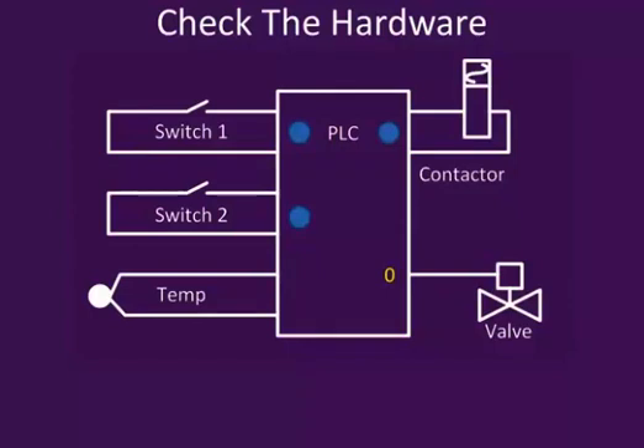Analog outputs are best checked through the software. All PLCs allow you to manually enter a value. It's called forcing. You force the output to 0. Then you go to the valve, or you have someone else at the valve, and he checks that the valve has gone to 0. Then you force the output to 50%, and you check the valve goes to 50%. Then you force it to 100, and you check it goes to 100. This way you've checked the range. Then you force it back to 50 and check the valve goes back to 50.